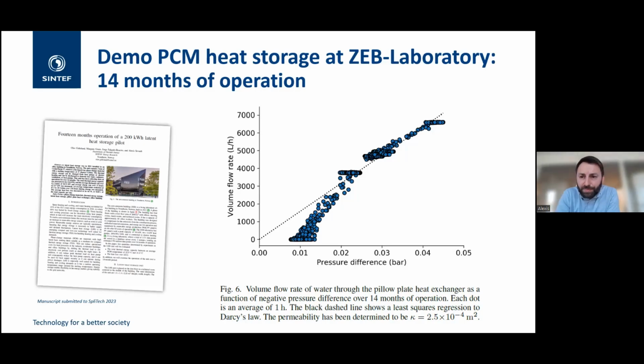So the pressure drop is not really a handicap in that case, but the same architecture that we have, we want to run it, for example, with CO2 systems, high pressure CO2 systems for refrigeration. And in that case, the pressure drop will be somehow an important data, especially when you upscale the system to several megawatt hour, to know how much energy you will consume to keep the pressure up and running in the whole system. So we want a heat exchanger that doesn't cost too much in terms of pressure drop. And so here we could at least characterize a bit the pressure drop depending on the water flow rate. That was quite interesting, and it's still very, very low. So that's a very good thing.